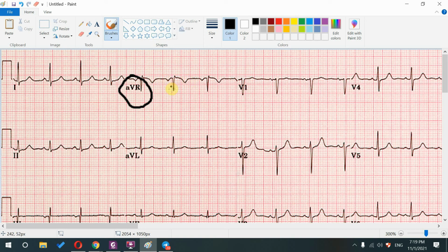See, the P wave is negative, the QRS complex is negative, and the T wave is negative. What does that mean? It means that you have installed the ECG machine correctly. If any of these is positive, it means that you have put it on upside down, basically. You put the leads in the wrong place. So after you look at this, you see all of them are negative, you are like, cool.